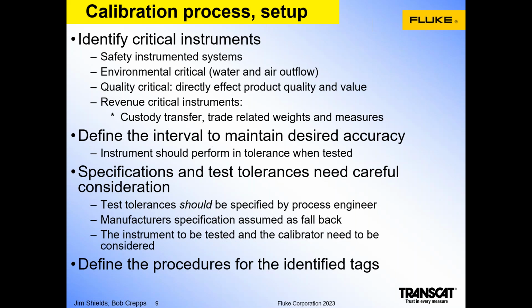And of course, the specifications and test tolerances need to be carefully considered. The test tolerances in process should be specified by the process engineer that was involved in the initial design of the plant and documented in such a way that that information can be passed down to the technicians that are doing the maintenance and calibrations. If that test tolerance documenting the allowed deviations for the process is not specified by the process engineer, oftentimes the instrument manufacturer's specifications data sheet is assumed as a fallback. That is not the ideal process and sometimes can end up in over calibration of those process instruments.